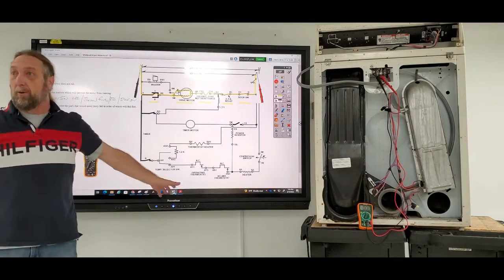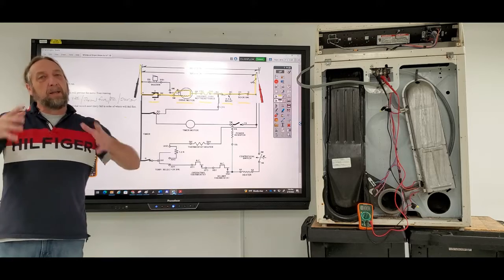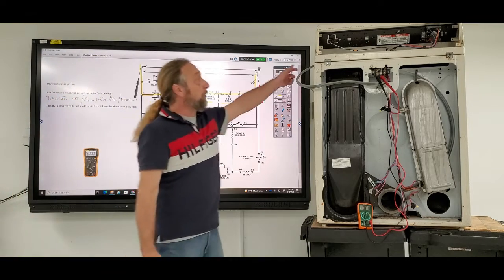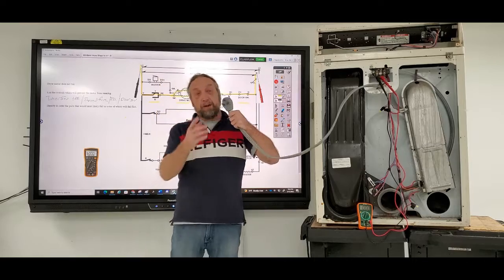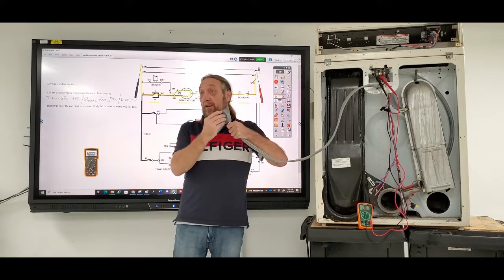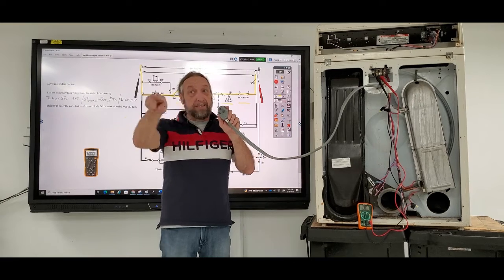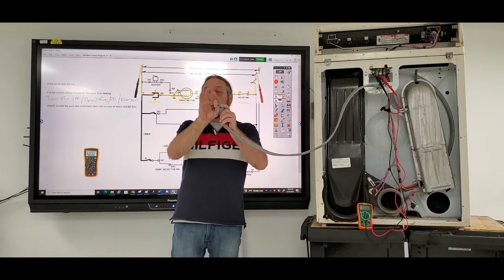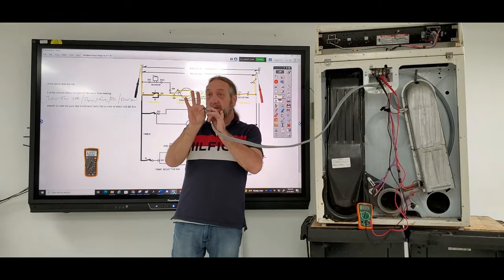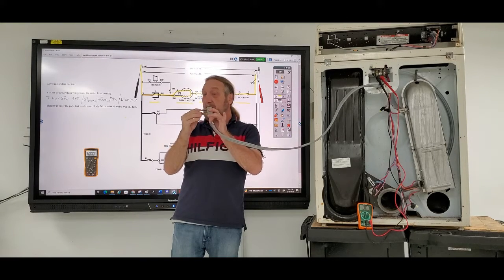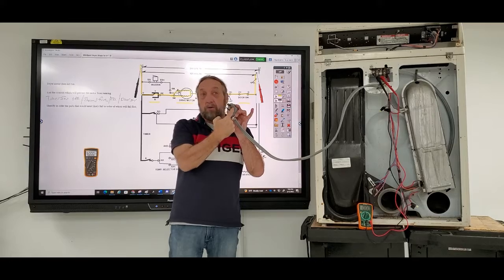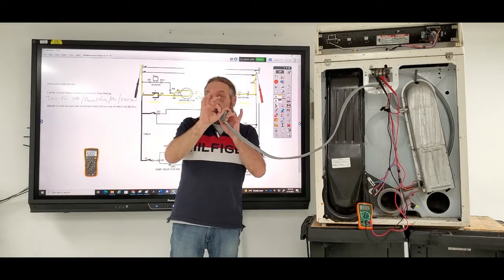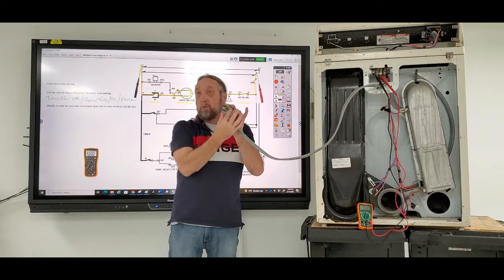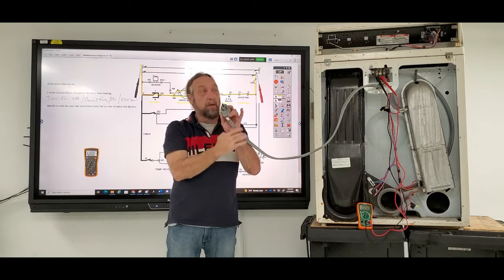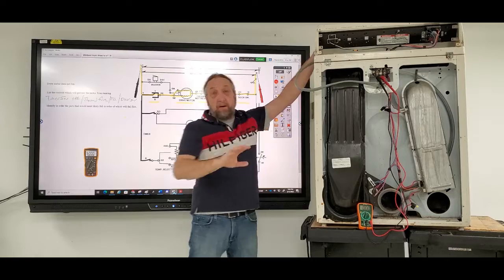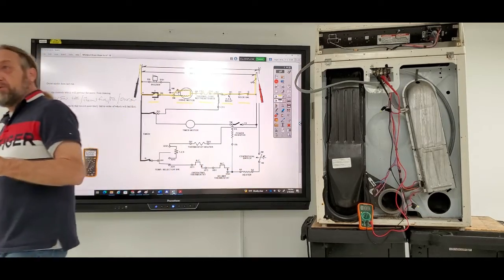I'm going to see if the motor's got power. But first, do we have proper power? On a 240 volt outlet, we could check the voltage where it goes into the outlet, but you need long enough meter leads. Or, if you back the plug off just a little, it's still making connection inside, so you can touch the metal prongs with your meter while it's still plugged in and check for 120, 120, 240. So again, verify the problem before taking panels off.